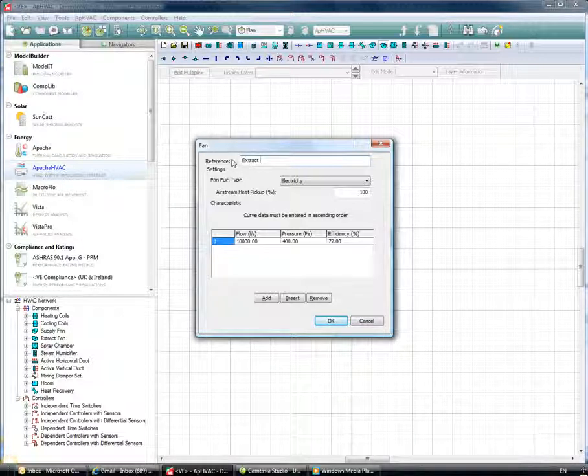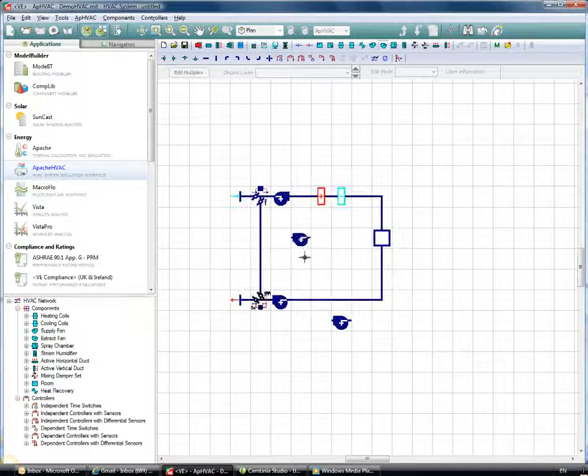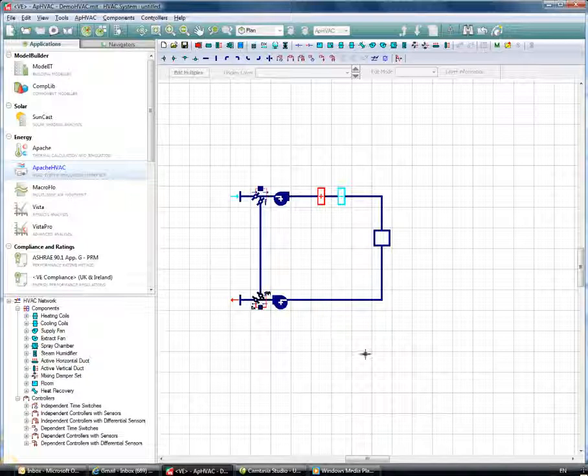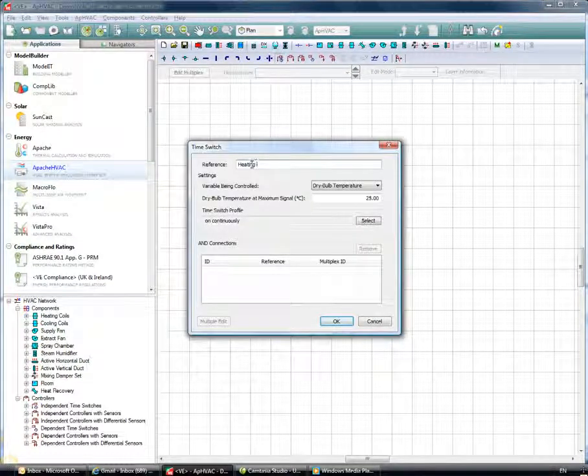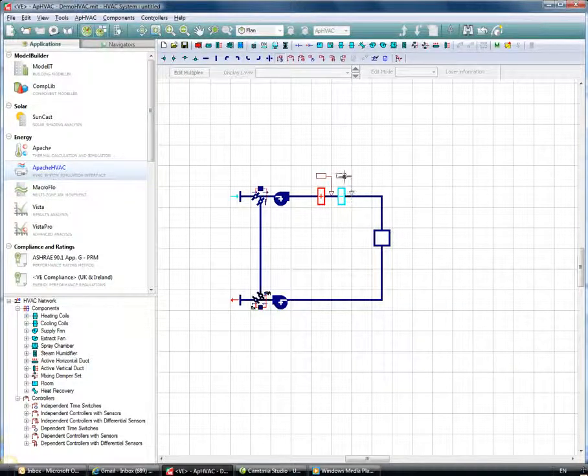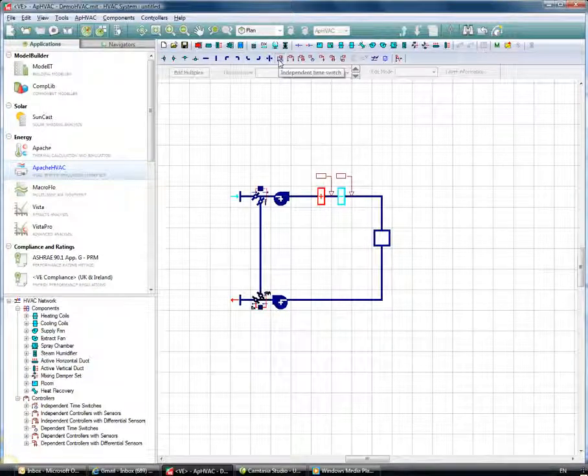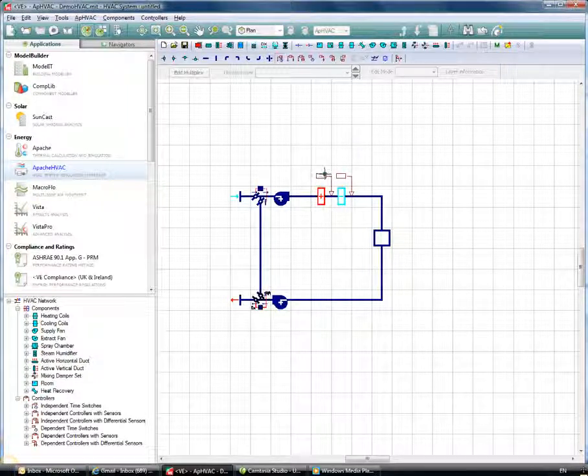I'll put in an extract fan — without going into as much detail as with the supply fan. For a constant volume system you'd have just one point on the curve; for a variable volume system you'd have more points. I'll just call this 'Extract Fan' and click OK. Starting with the heating and cooling coil controllers, I'll choose an independent time switch, set a dry bulb temperature of 14°C for the heating coil, and do the same for the cooling coil — dry bulb temperature of 14°C. These two time switch controllers control the off-coil temperatures to 14°C.